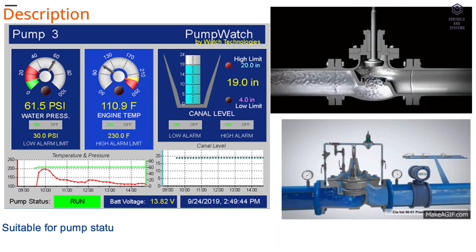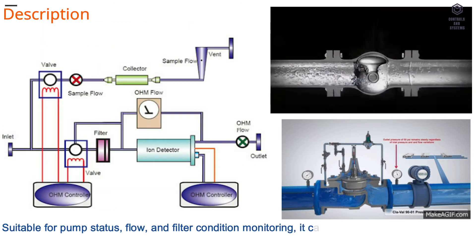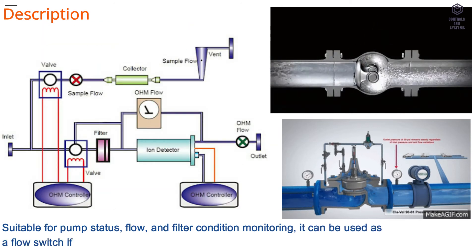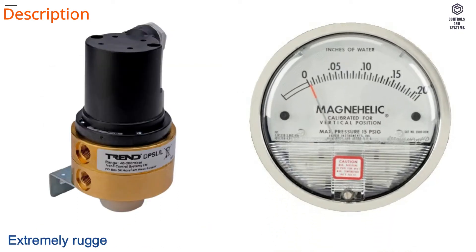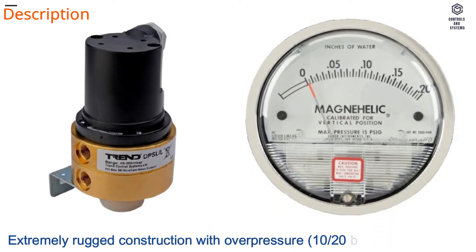Suitable for pump status, flow, and filter condition monitoring, it can be used as a flow switch if fitted across an orifice plate. Extremely rugged construction with overpressure 10/20 bar safety margin.